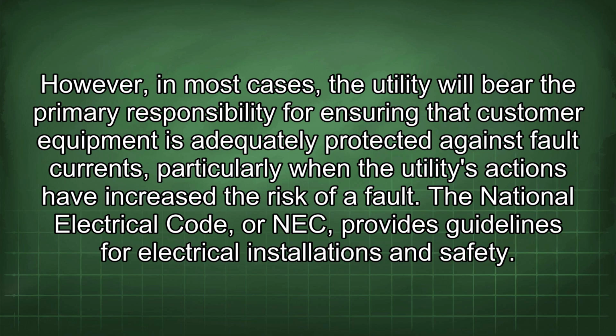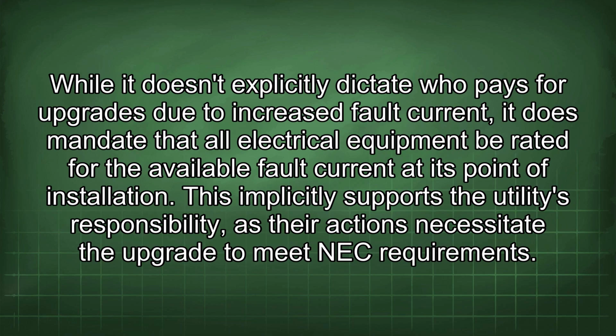The National Electrical Code, or NEC, provides guidelines for electrical installations and safety. While it doesn't explicitly dictate who pays for upgrades due to increased fault current, it does mandate that all electrical equipment be rated for the available fault current at its point of installation.